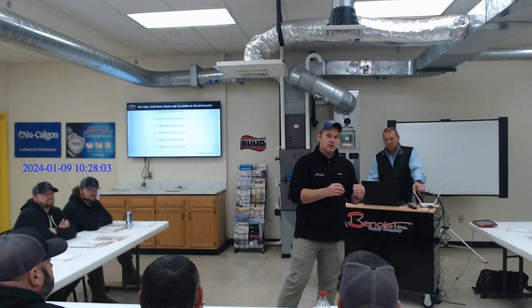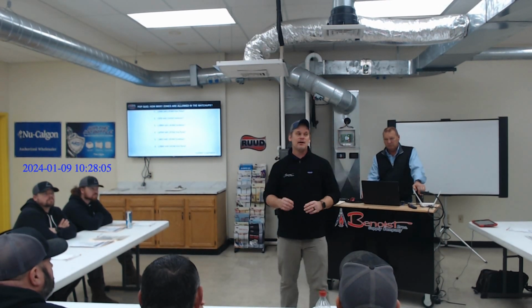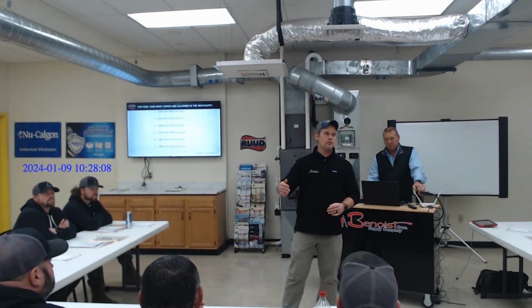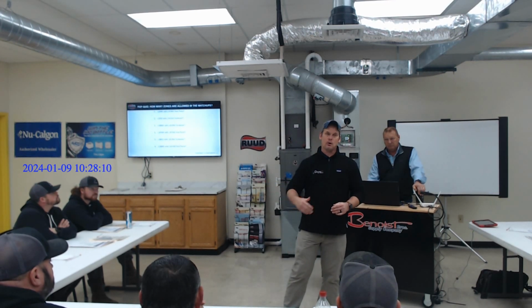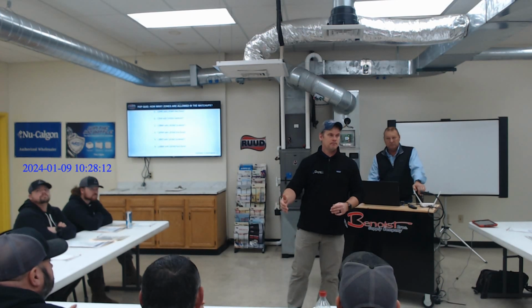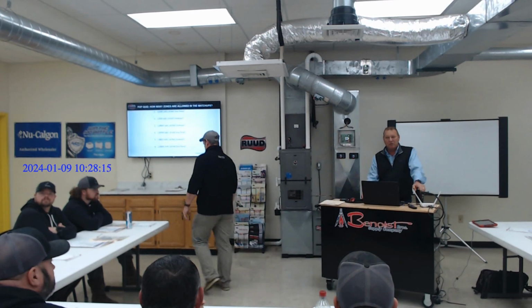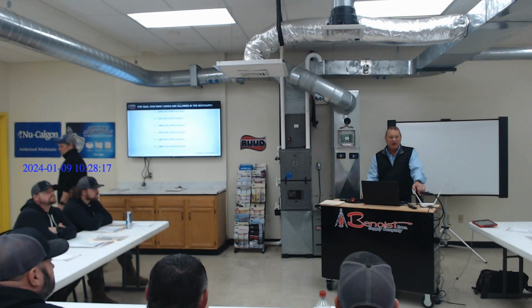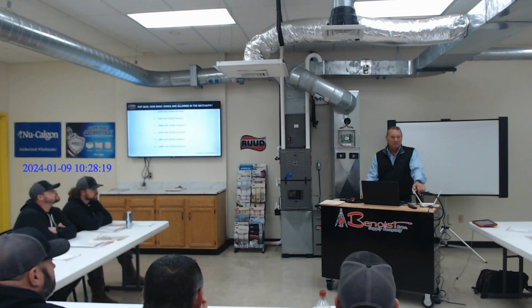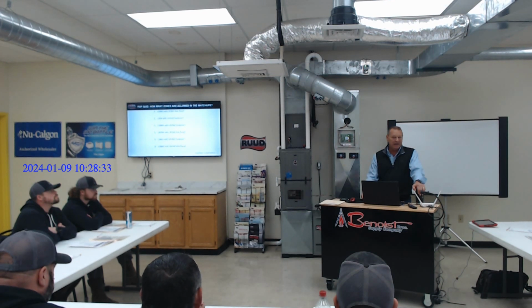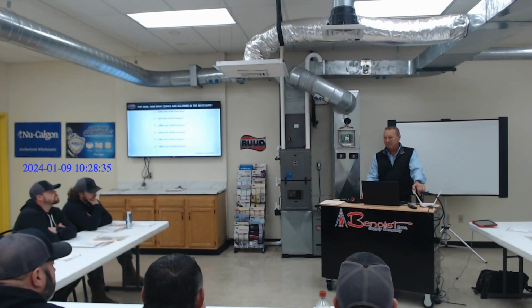We're trying to explain where you could get a little bit, but at the end of the day, we have to walk in and look at our ductwork when we're sizing our jobs or when we're doing our changeouts. You know what I mean? By the way, if I put a 20 kW in a 4-ton air handler, I have no choice for airflow. You're going to need at least about 1600 CFM if all 20 kW of electric heat kicks in. And if you don't, you're going to have limit trips, you're going to have all kinds of issues with that electric heat. I cannot adjust that electric heat CFM.